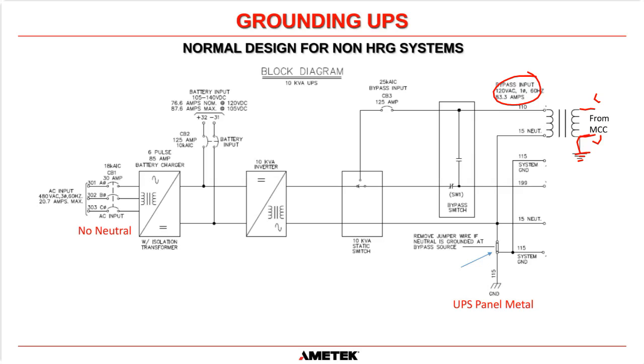So on the secondary side, so this is the primary and this is the secondary side. On the secondary side, as drawn here, we have no connection inside the UPS between neutral and ground. So in this circumstance, you would leave this jumper in this position. That's not what we recommend, but if this is how you've run your bypass supply to the UPS, you would leave this jumper in place to connect system ground and panel ground to the output neutral of the system. That's what that jumper bar is doing.